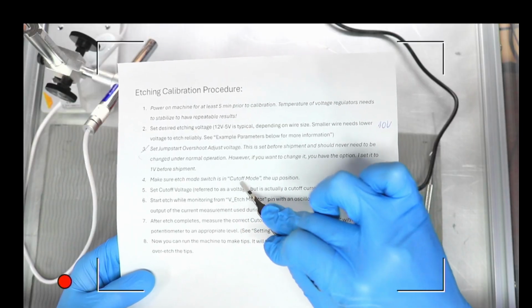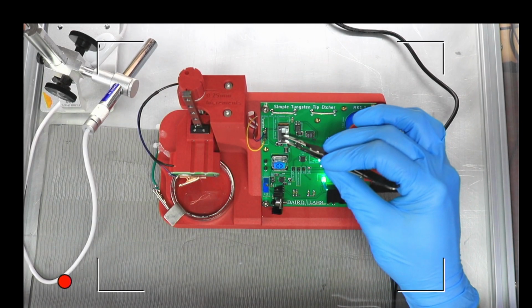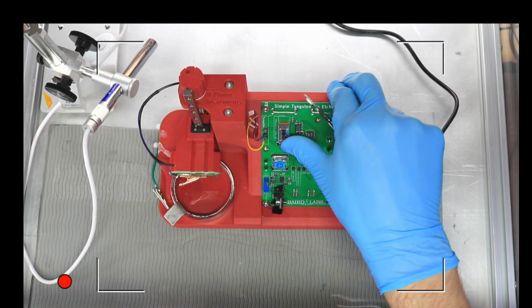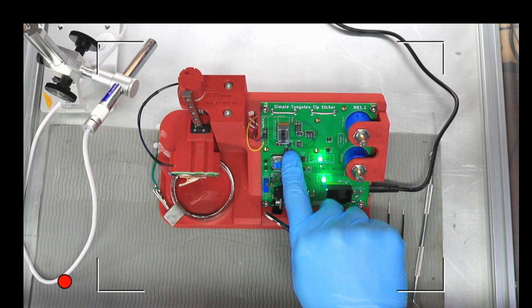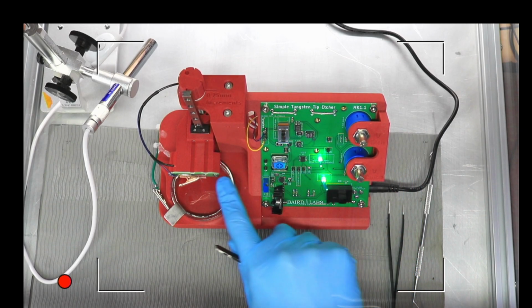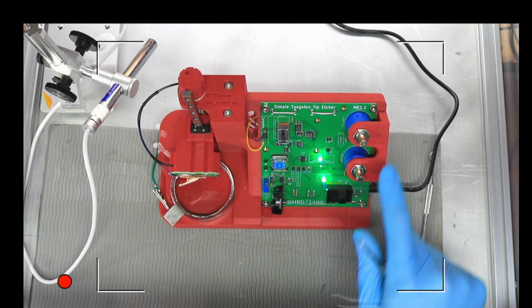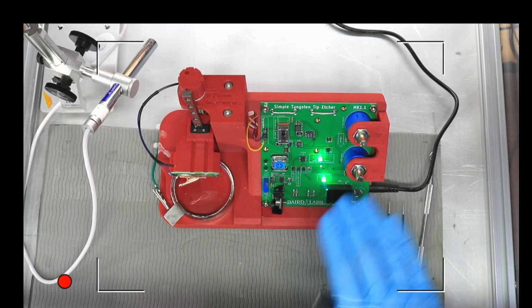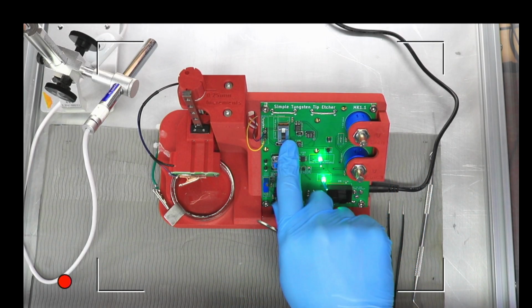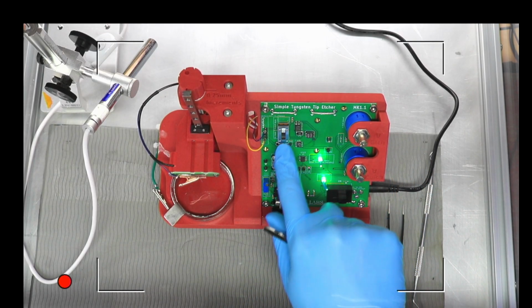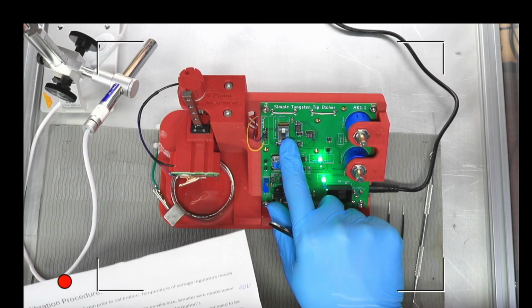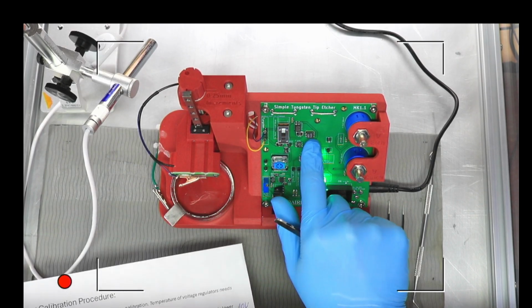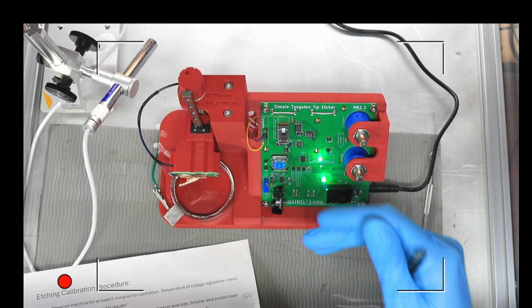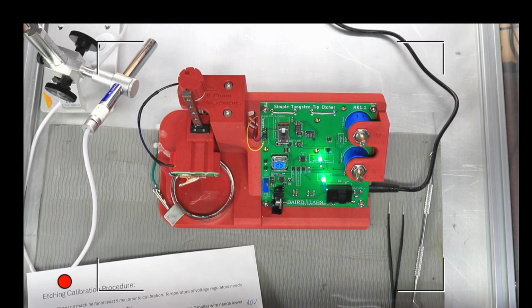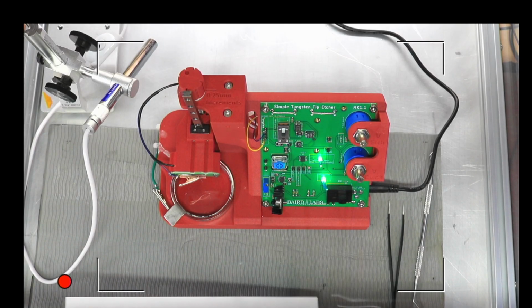Make sure the mode switch is in cutoff. That's this switch here. There's two different settings. The bottom setting is on, and that just applies a constant voltage to the tip. That's just whatever the etching voltage is, always applied on the tip. But we want to operate in cutoff mode, so we'll leave it in cutoff. The reason why we want to do the calibration in cutoff rather than just in on is these MOSFETs have some voltage drop associated with them, and we want to make sure that we're taking that into account whenever we do the calibration.